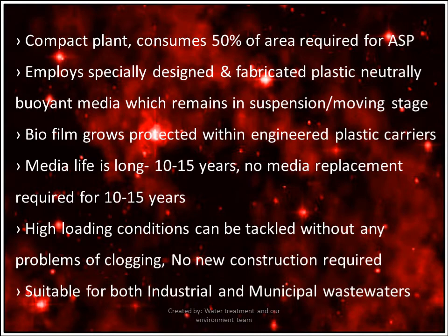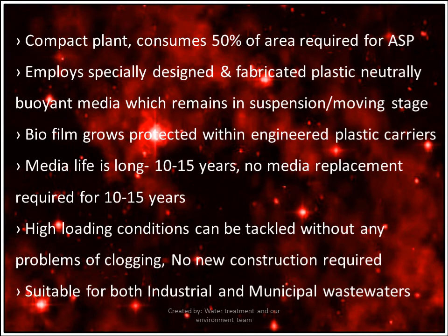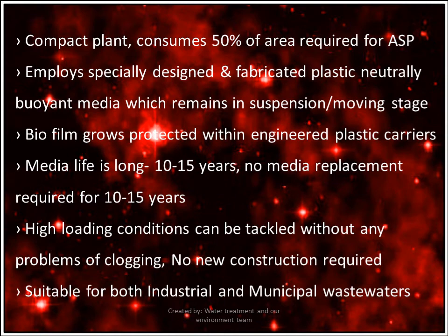Advantages of MBBR include its compact plant footprint, consuming only 50% of the area required for an activated sludge process. It employs specially designed plastic media which remains in suspension and in a moving state. Biofilm grows protected within the engineered plastic carrier. Media life is long, around 10–15 years, so no media replacement is required during that period. High loading conditions can be handled without any problem of clogging.